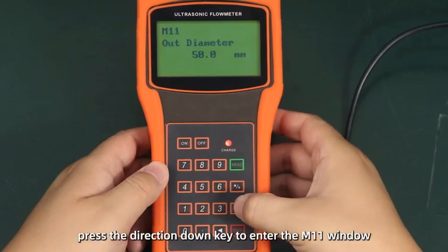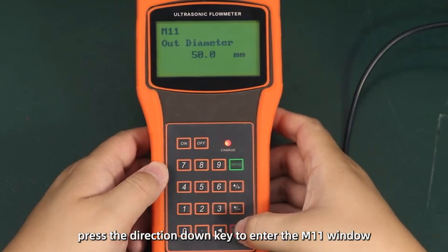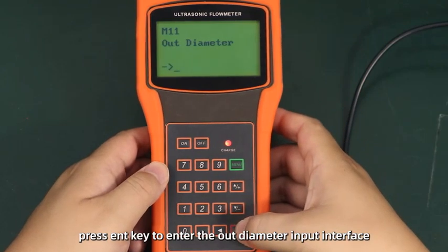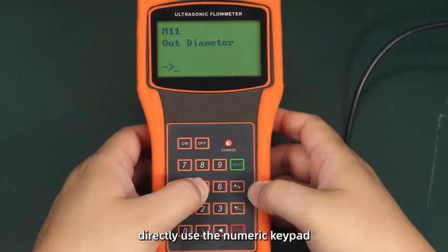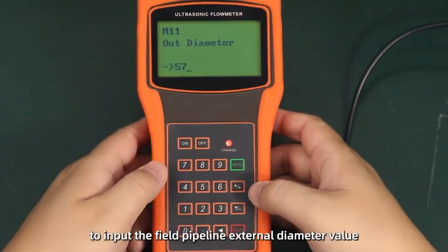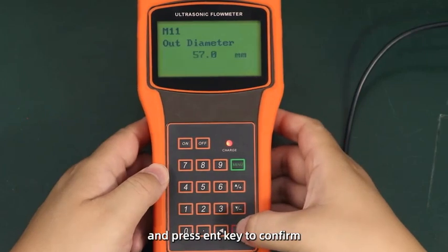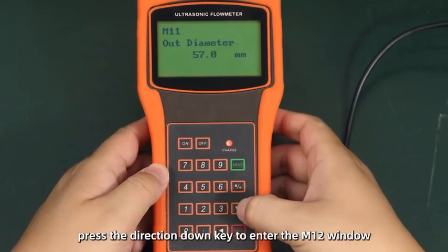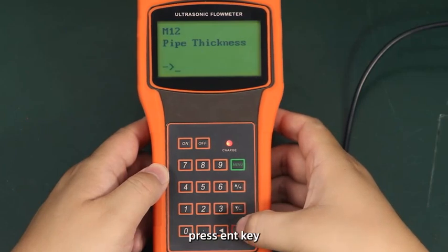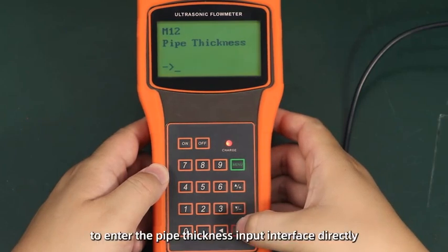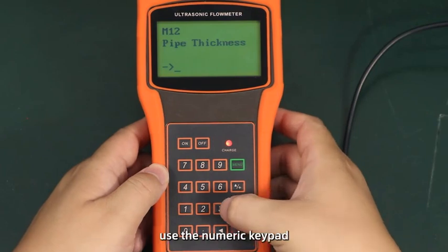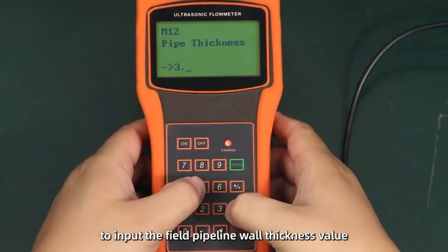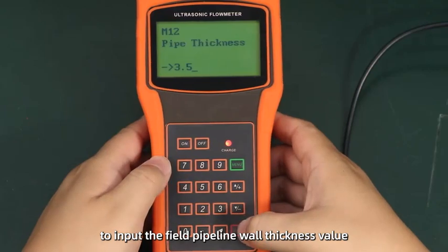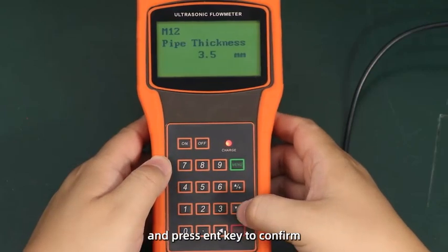Press the direction down key to enter the M11 window. Press ENT key to enter the out diameter input interface. Directly use the numeric keypad to input the field pipeline external diameter value, and press ENT key to confirm. Press the direction down key to enter the M12 window. Press ENT key to enter the pipe thickness input interface. Directly use the numeric keypad to input the field pipeline wall thickness value, and press ENT key to confirm.